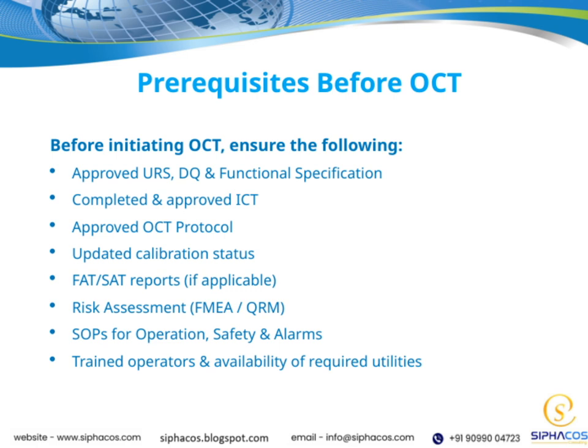We also need to verify that the calibration status of our instruments is up to date, ensuring accurate measurements during testing. If applicable, FAT and SAT reports should be finalized. These validate that the equipment has passed factory acceptance testing and site acceptance testing. Risk assessment is another critical point. Tools like FMEA or QRM should be completed to identify and mitigate potential risks early on.